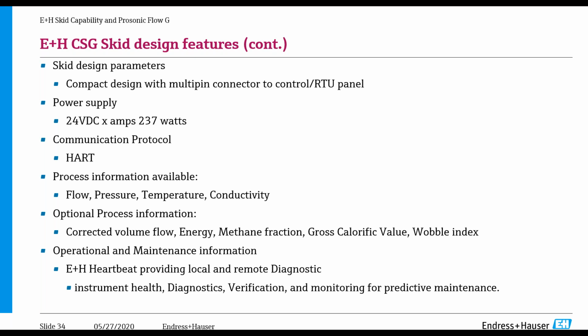Flow and pressure can be measured directly on our flow meter on the gas line, but on the separator we have a standalone pressure transmitter. Temperature is integrated into the G300, so we can get a temperature measurement from the G300, and the G300 is also able to measure conductivity. There are a number of other process variables that can be measured using the G300 and are available as an option.